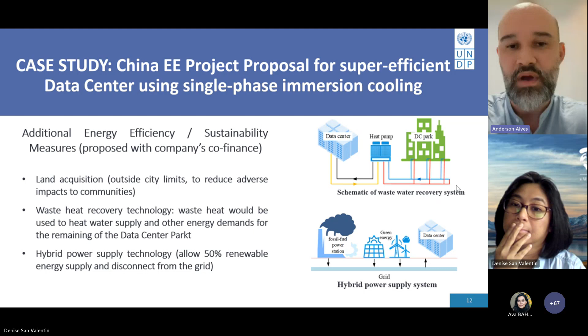Considering the theoretical model based on the power usage effectiveness, which is the main metric used to determine the energy efficiency of a data center, the closer this PUE is to 1, the more efficient the data center is. Starting from the baseline technology, air-to-air, with 7,200 kilowatts of power and a PUE of 1.5, with this tested technology we were hoping to achieve a PUE of 1.1, a huge increase in energy efficiency. You can see the amount of energy consumption reduced, from almost 1,900 gigawatt hours to 1,300 gigawatt hours.